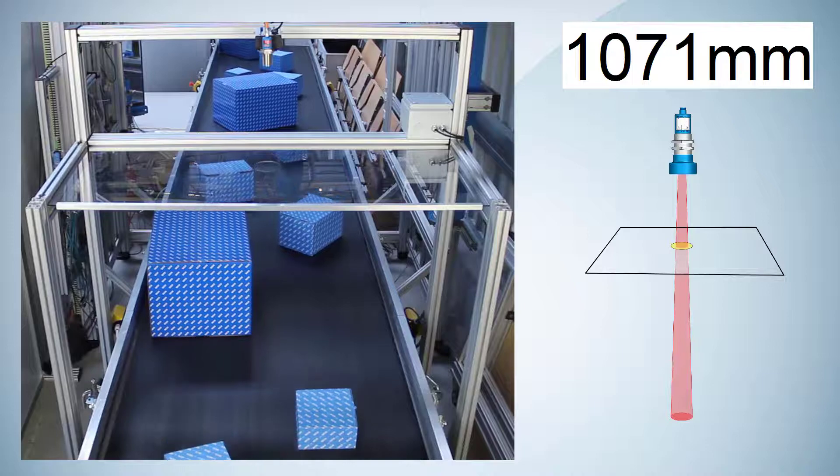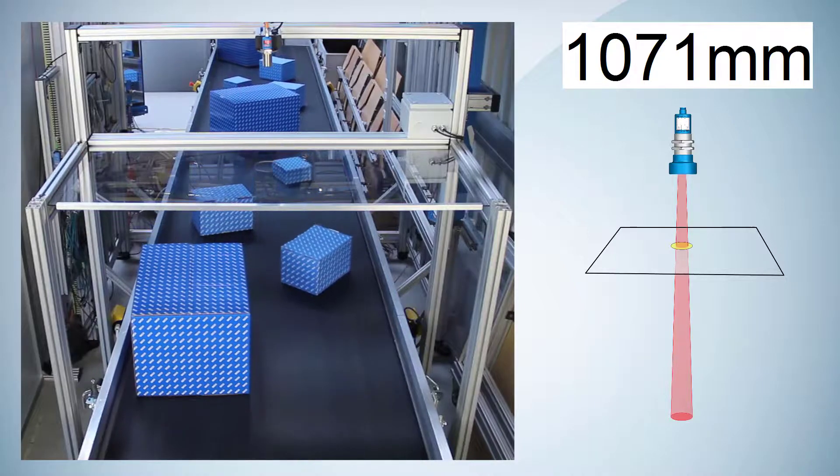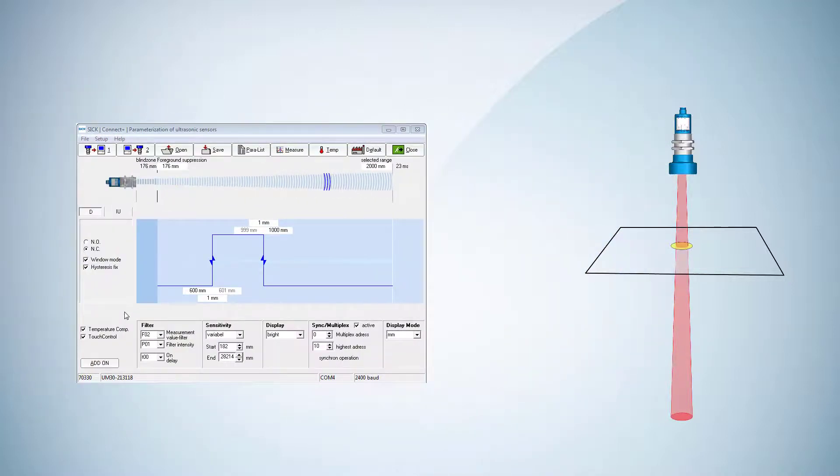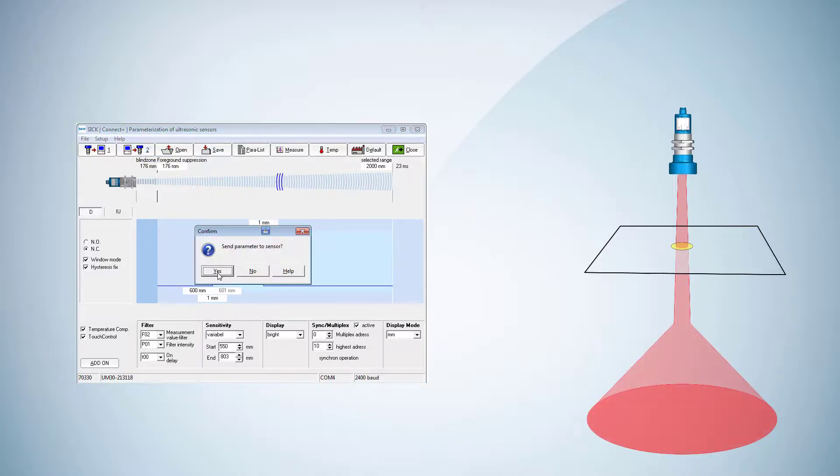To include all the boxes on the conveyor belt, we have to go once more into the software Connect Plus. We set the start value of the amplification increase below the acrylic glass and the end value close behind to have the highest sensitivity below the glass. We set the start value to 550 millimeters and the end value to around 800 millimeters and send the data to the sensor.